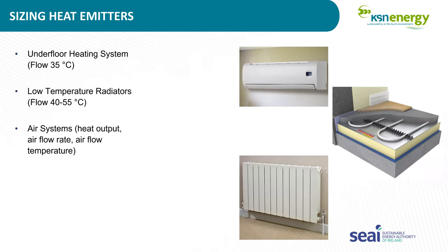When it comes to sizing the heat emitters, look, underfloor heating is great. It's low temperature anyway. The next thing, low temperature radiators and fan coil units, can work at low temperatures, typically 40 to 55 degrees. For air systems, for an air-to-air heat pump, the emitters are given and they're part of the system, so the sizing of that doesn't really matter too much.